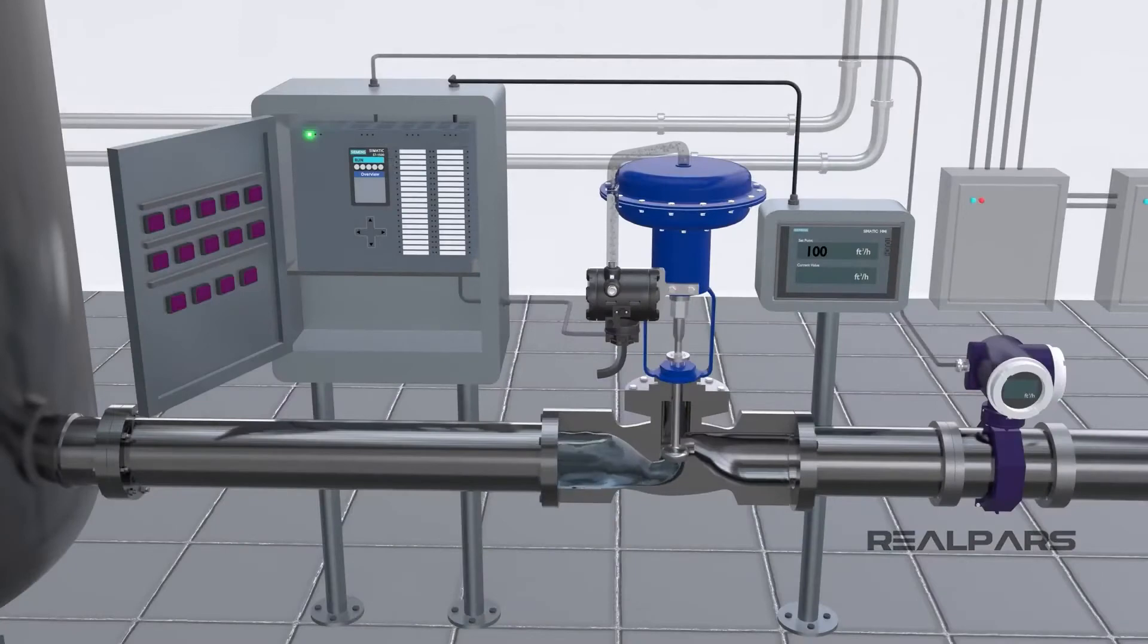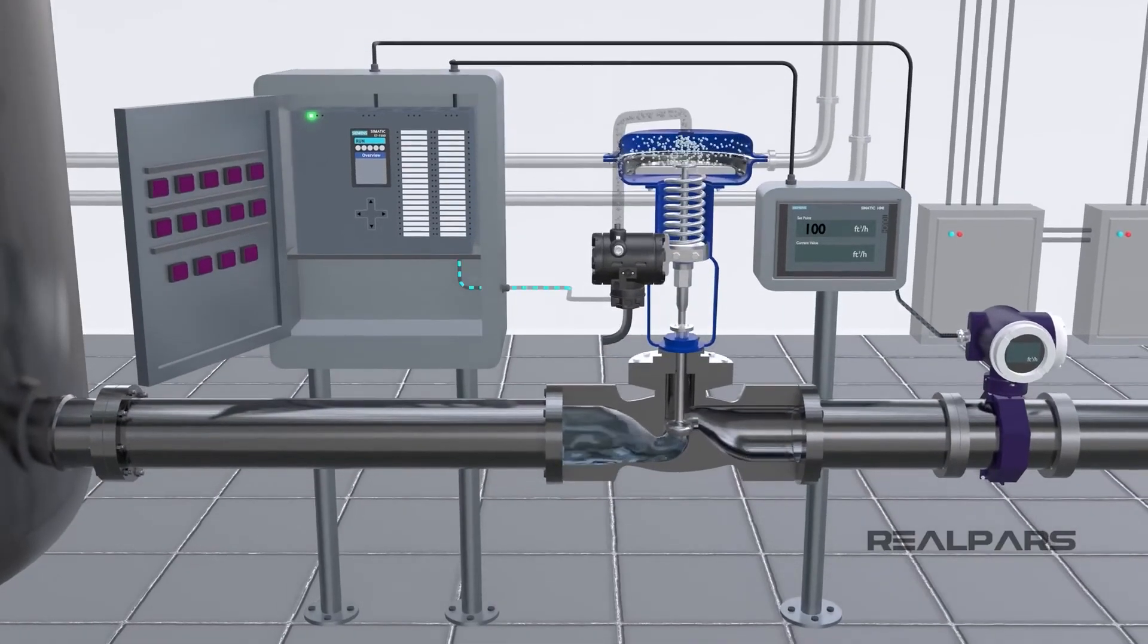The control valve receives a signal from a controller, such as a PLC or a DCS, in order to operate. The controller compares the actual flow rate to the desired flow value, called the setpoint. The controller will produce an output to move the valve to bring the flow rate to the setpoint value. Because of how pneumatic actuators are built, a control valve will fail to a specific position when a loss of the control signal occurs.